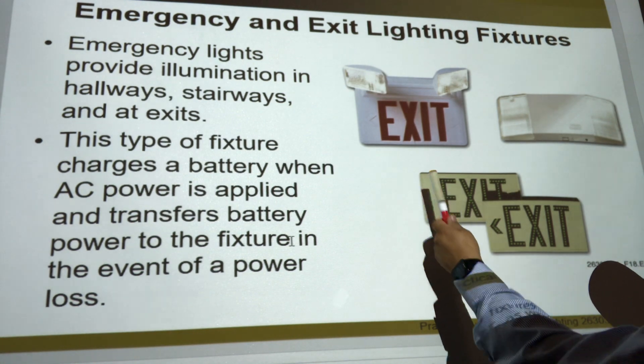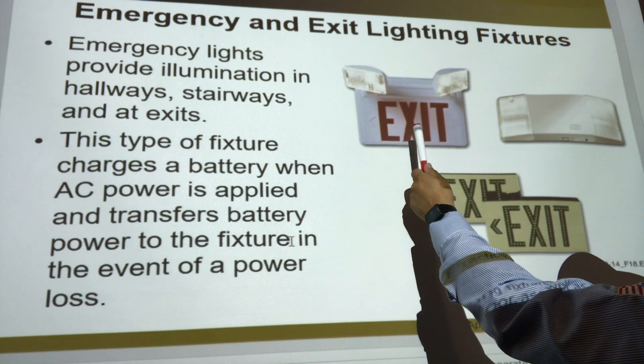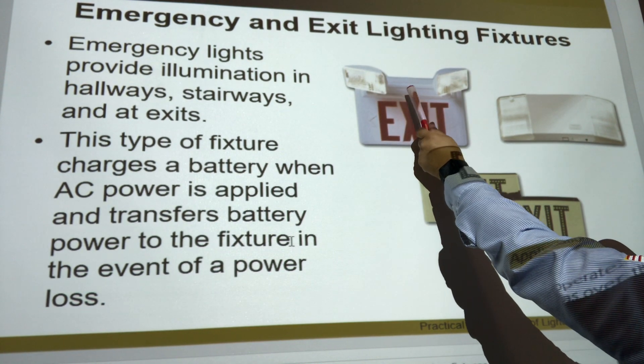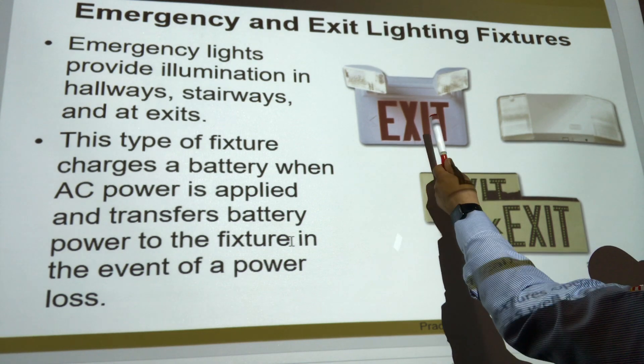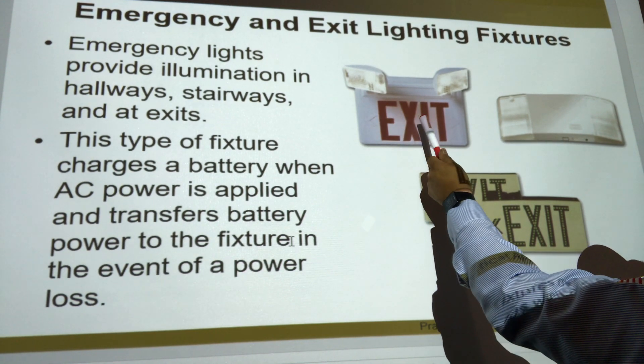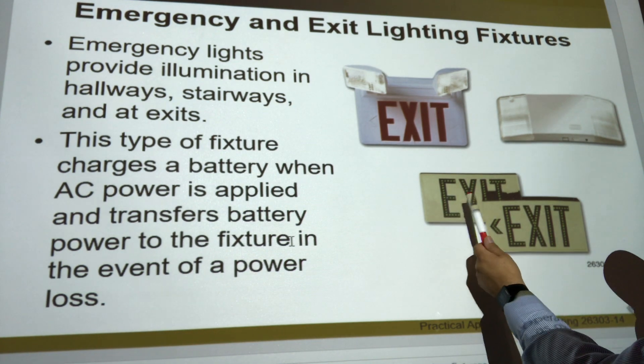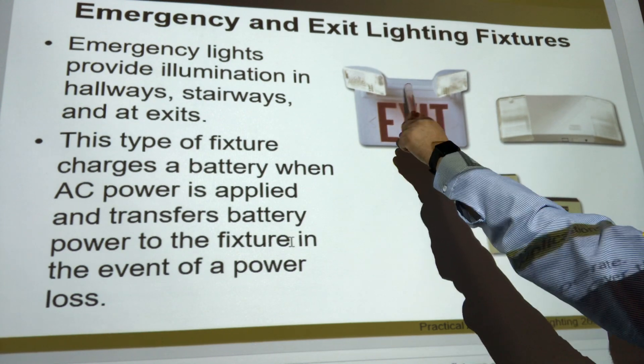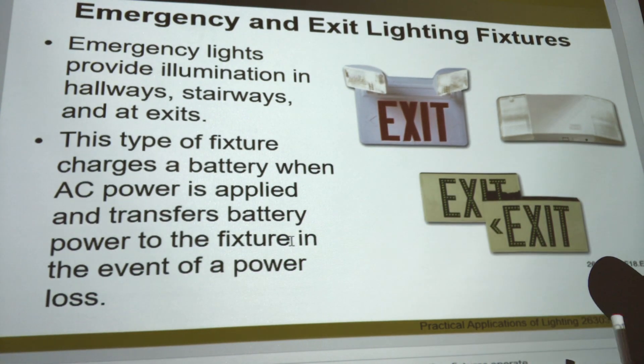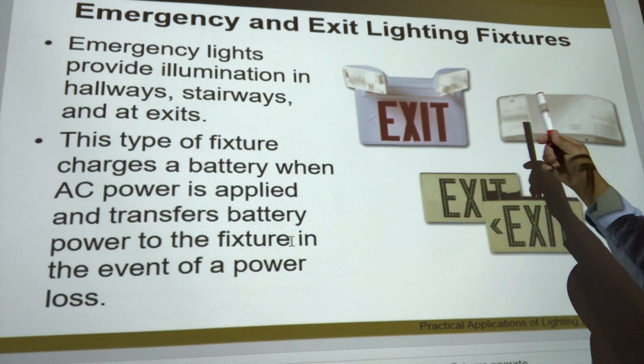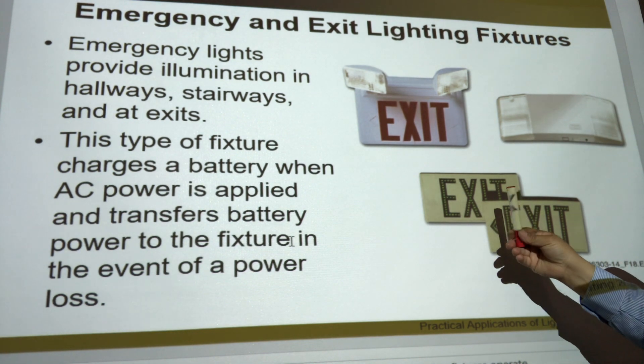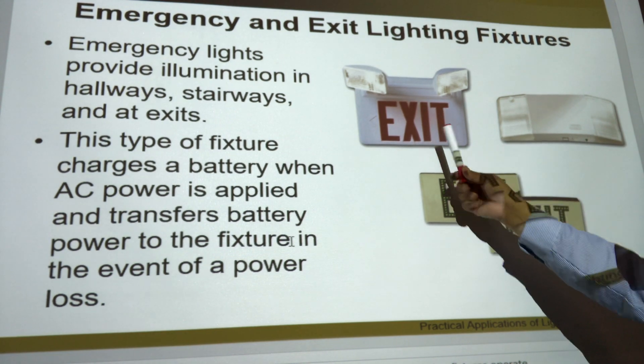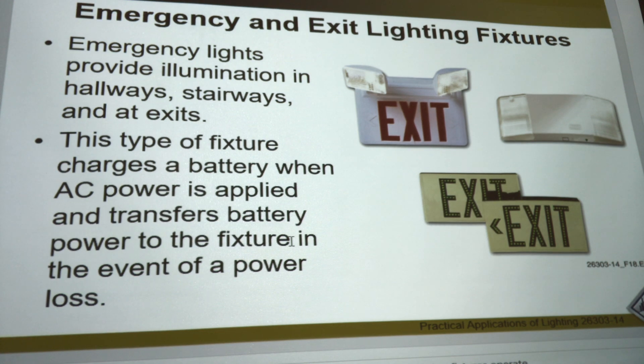Exit signs — everything is LED now. Emergency lights only turn on when power goes out to the fixture. The exit sign itself is constantly lit up. When power dies, the emergency lights turn on. This is a combo pack — a combo exit sign and emergency light. You have to have a certain number of emergency lights in hallways for building egress, and exit signs are required. Whether it's red or green matters and is something you need to understand when installing.